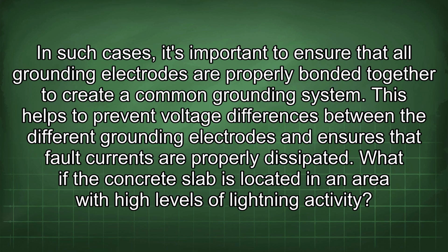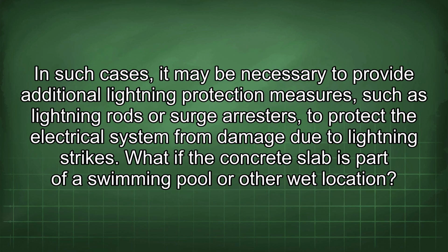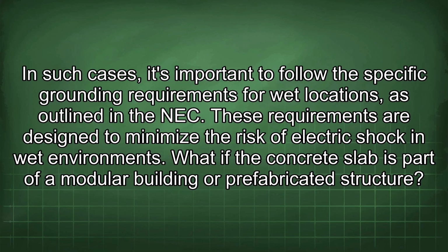What if the concrete slab is located in an area with high levels of lightning activity? In such cases, it may be necessary to provide additional lightning protection measures such as lightning rods or surge arresters to protect the electrical system from damage due to lightning strikes. What if the concrete slab is part of a swimming pool or other wet location? In such cases, it's important to follow the specific grounding requirements for wet locations as outlined in the NEC. These requirements are designed to minimize the risk of electric shock in wet environments.